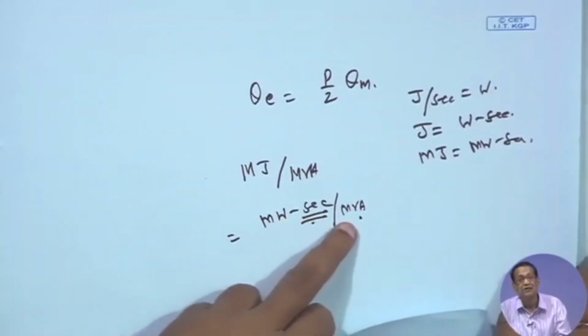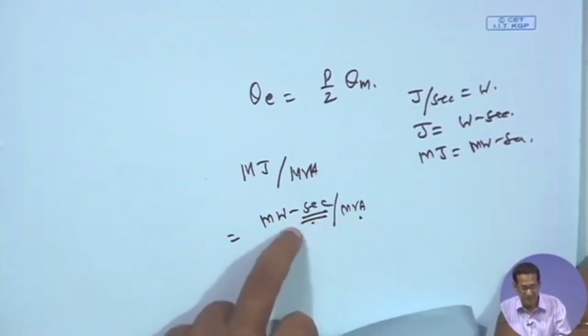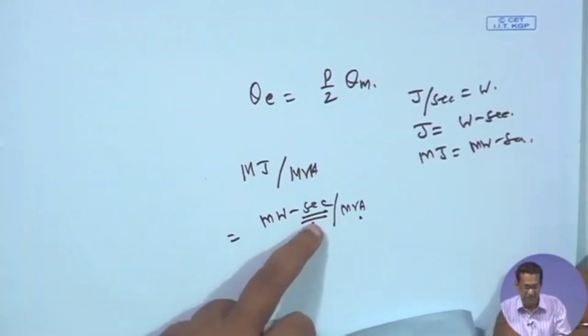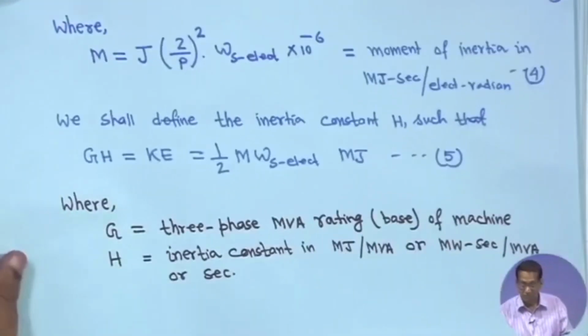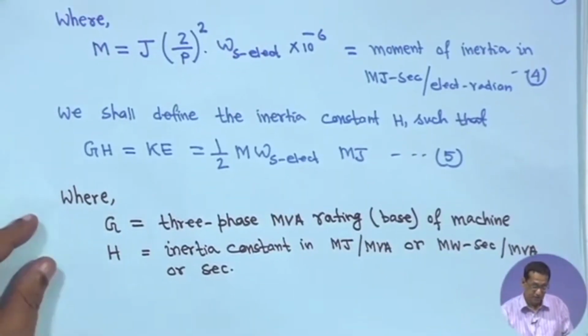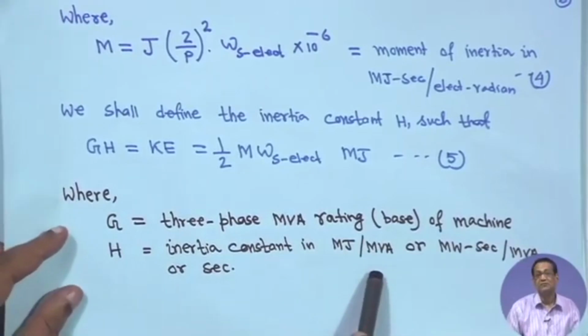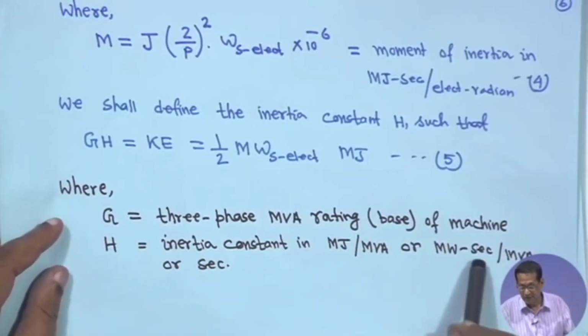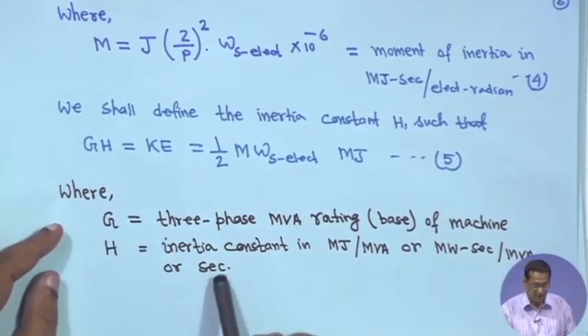Since MW/MVA is dimensionless, it is given in seconds. So the inertia constant H in megajoule per MVA is the same as megawatt-second per MVA, or simply second.